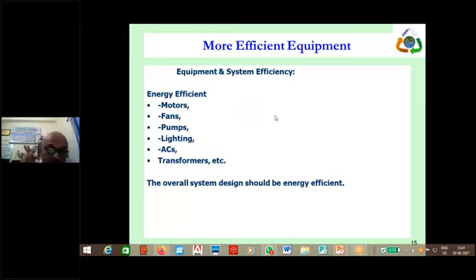Once you address the overall system design, then you can later on say confidently that yes, this whole water pumping system is, say, pipe sizing is correct, routing is correct, and other connected things are correct. Start with the user end. Where is that being used? So starting from the user end, come back and check, yes, the whole system is as per the need, as per the optimum design, and then I am seeing the pump is not an efficient one. So I am recommending change of the pump. Otherwise, just changing the pump may still not give you energy conservation. Same way, blindly replacing with energy efficient motors without seeing the connected equipment may not result in energy saving.